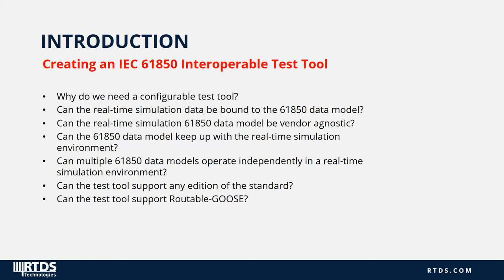Can the test tool support any edition of the standard? Can the test tool support routable GOOSE? Yes, any valid SCL file, as long as it is configured properly, can support edition 1, edition 2, and edition 2.1, as well as routable GOOSE.